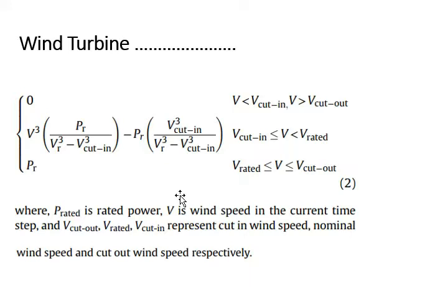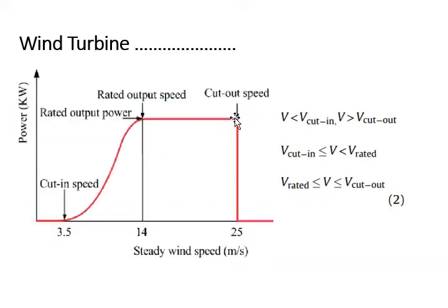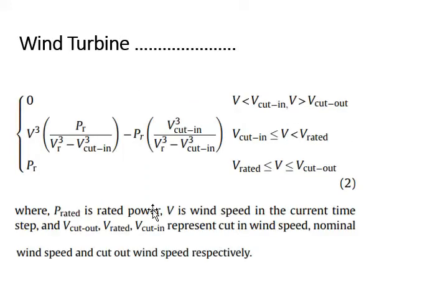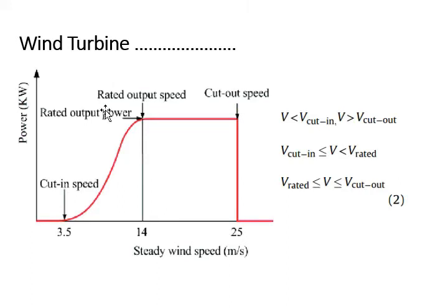We will discuss it in detail then, but for now consider it a cubic estimation, because the power is 3, a cubic estimation of the wind velocity power curve. When the velocity is between the rated speed and the cut-out speed, the output power will simply equal the rated power of that wind turbine. This is indicated here. So we have discussed the power curve of the wind turbine.